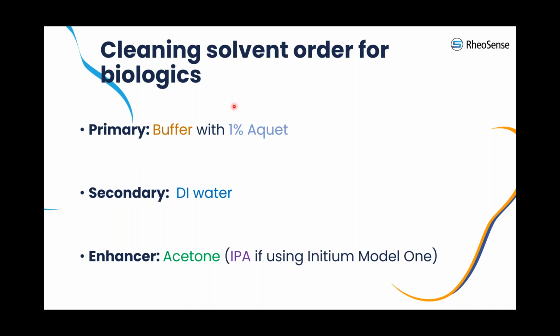My colleague was mentioning this earlier. And then the next slide shows exactly how this primary solvent is prepared. For those not familiar, in the past this primary solvent used to be only the formulation buffer itself, but we found that cleaning improved when we made this a combination of the buffer and Aquet.